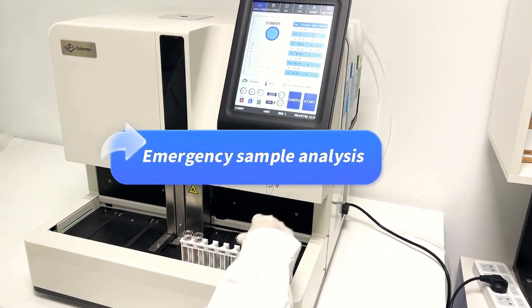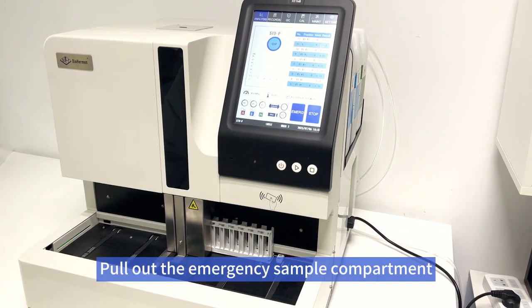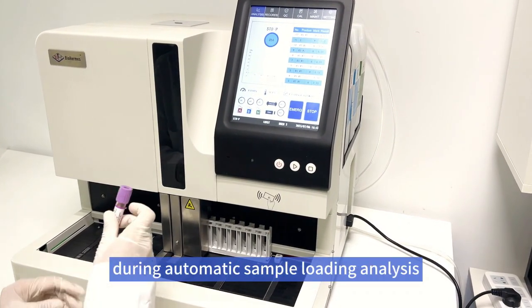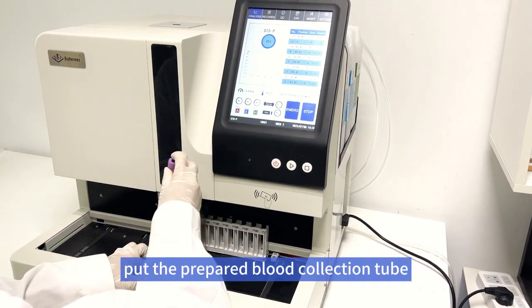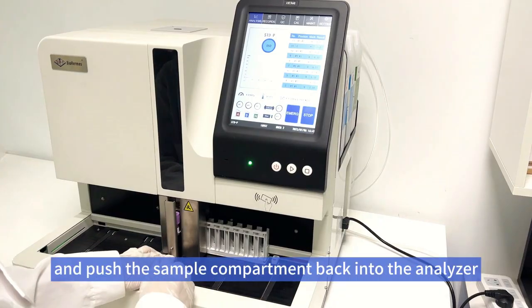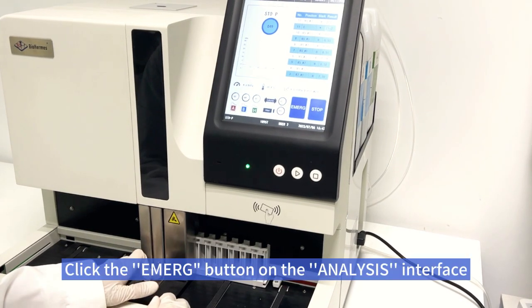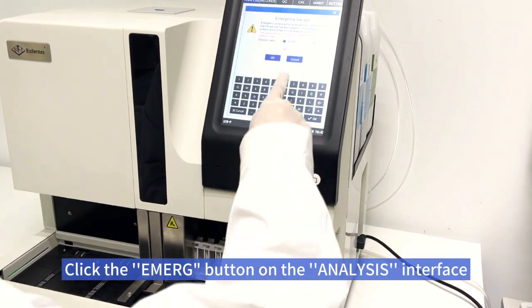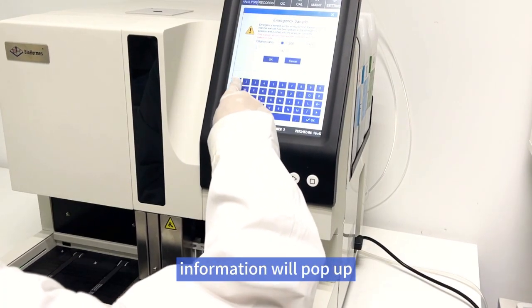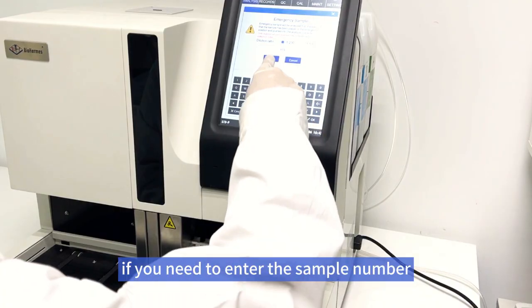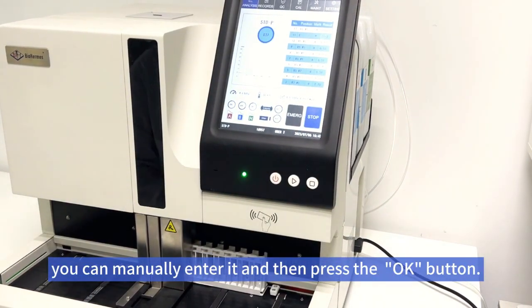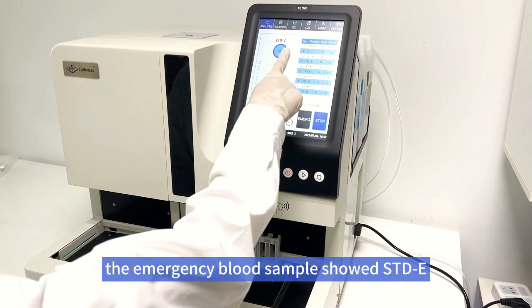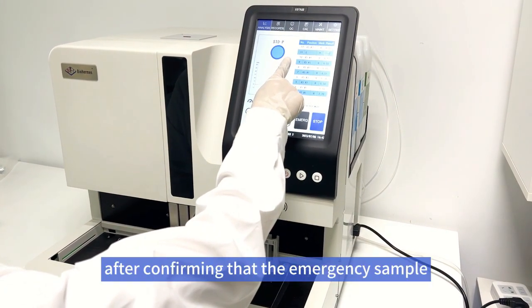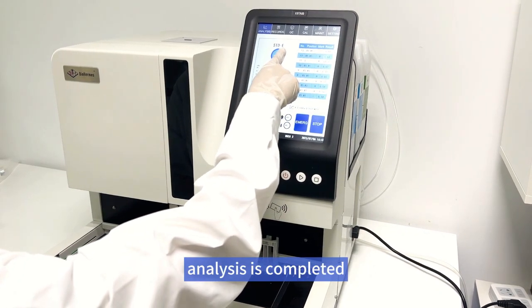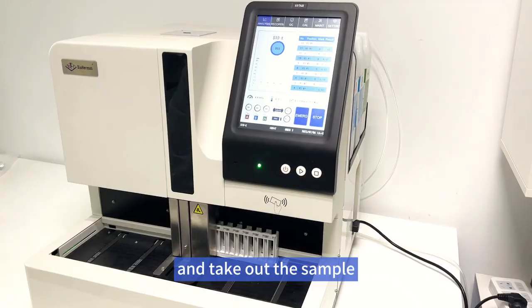Emergency sample analysis. Pull out the emergency sample compartment during automatic sample loading analysis. Put the prepared blood collection tube into the emergency sample compartment, and push the sample compartment back into the analyzer, and push it to the end. Click the Emerg button on the analysis interface, and the confirmation box of the emergency sample information will pop up. If you need to enter the sample number, you can manually enter it and then press the OK button. The emergency blood sample showed STDE. After confirming that the emergency sample analysis is completed, pull out the emergency sample compartment and take out the sample.